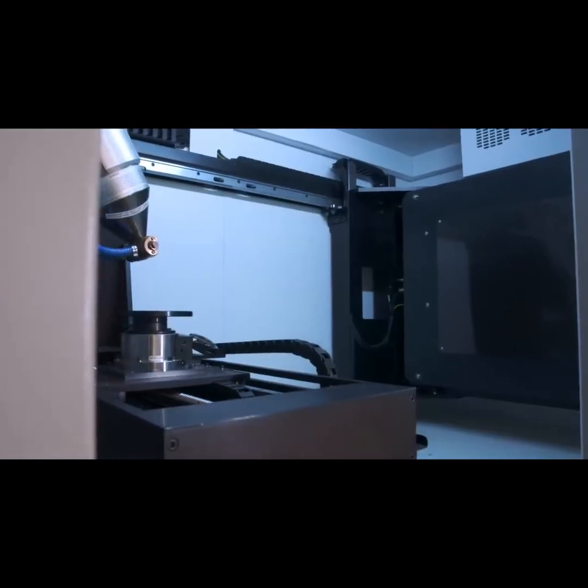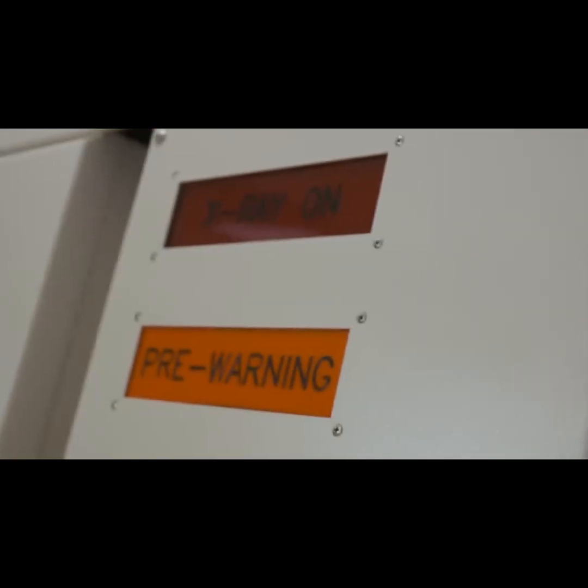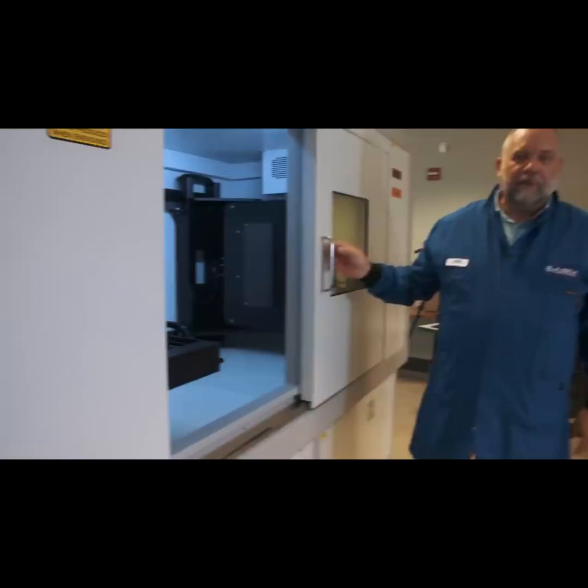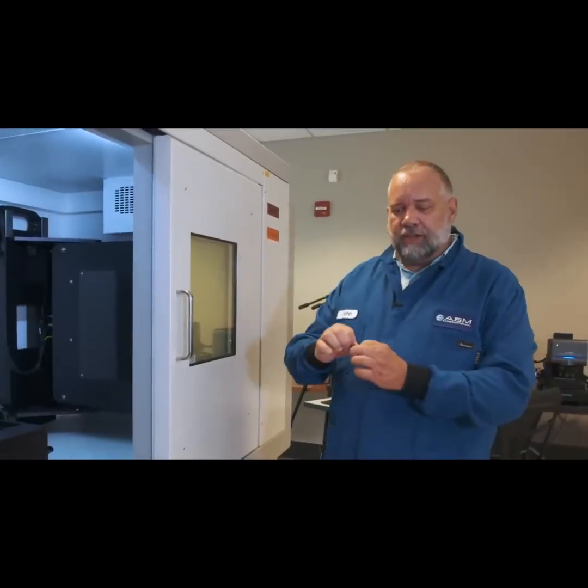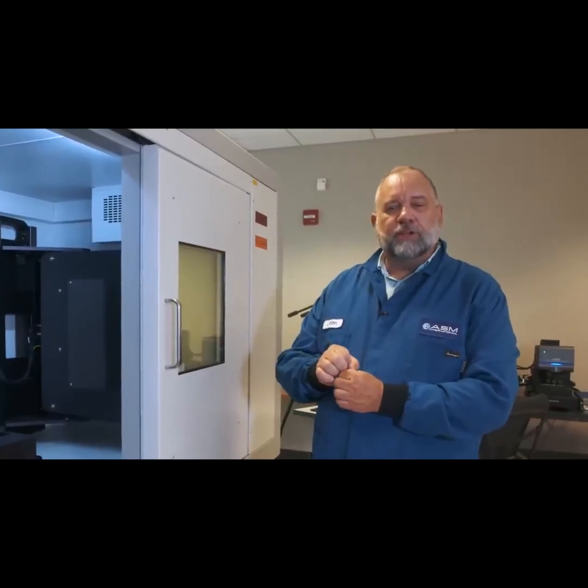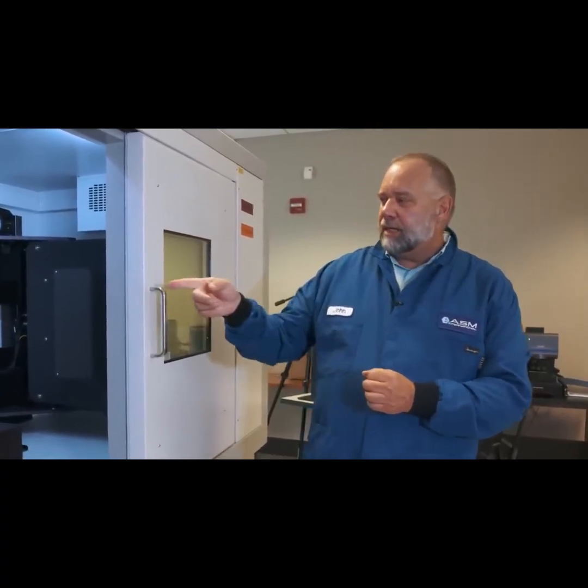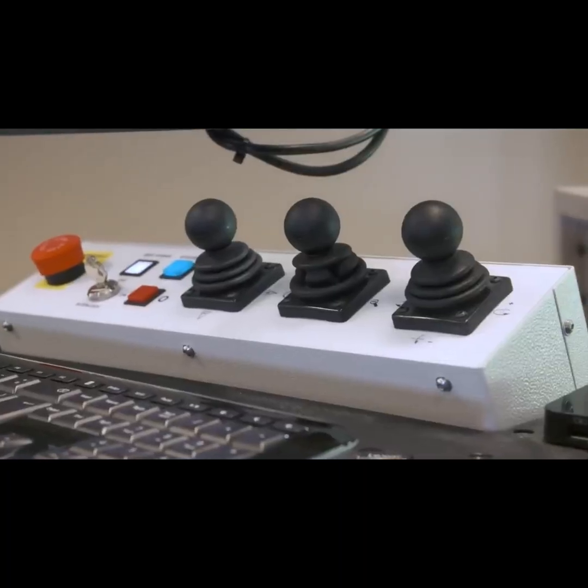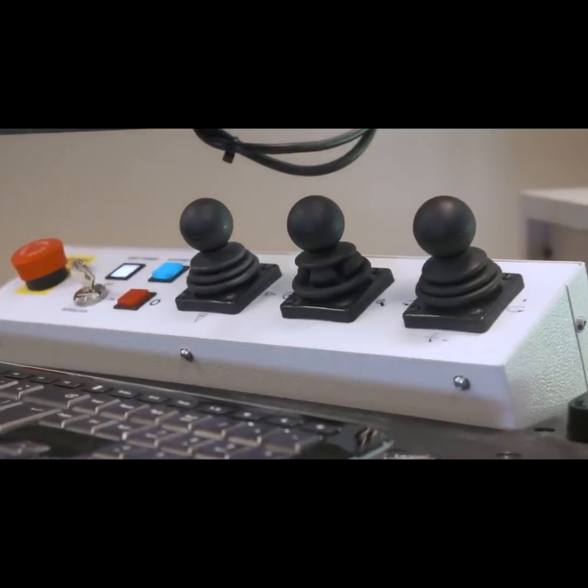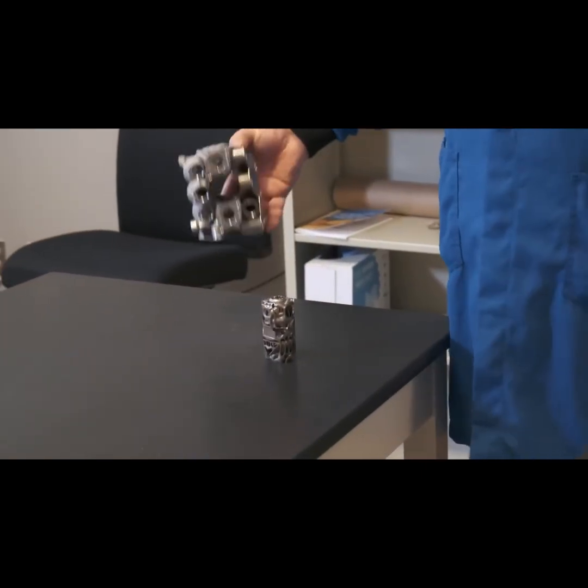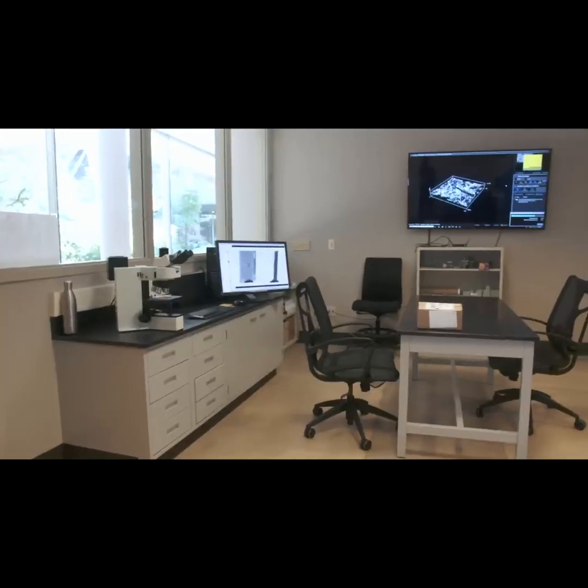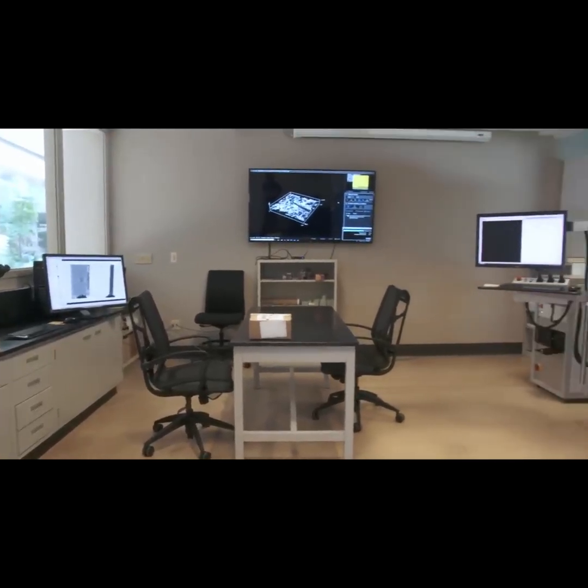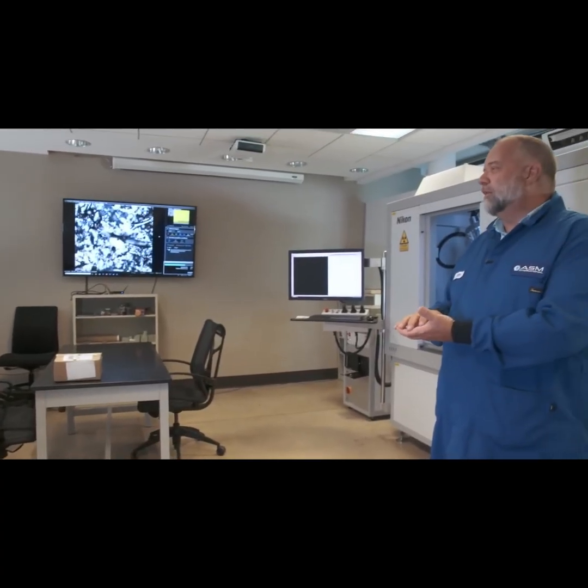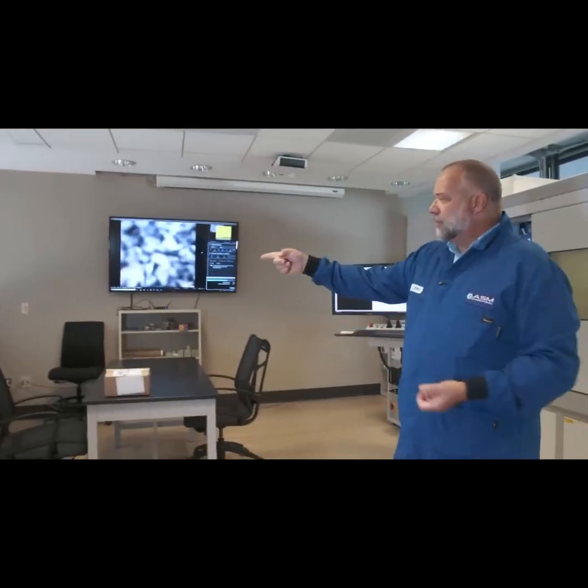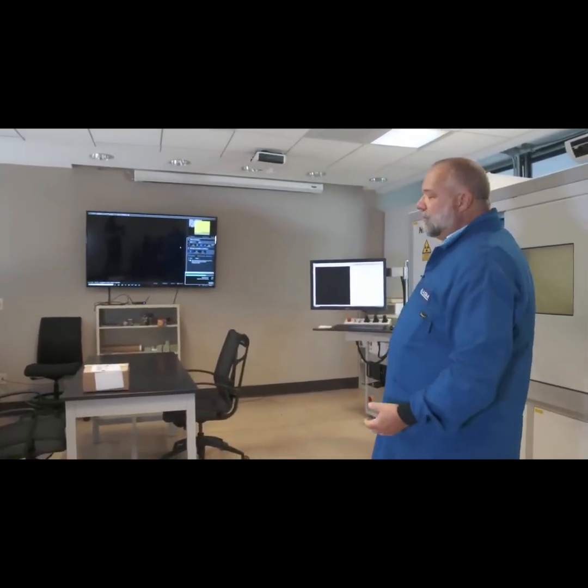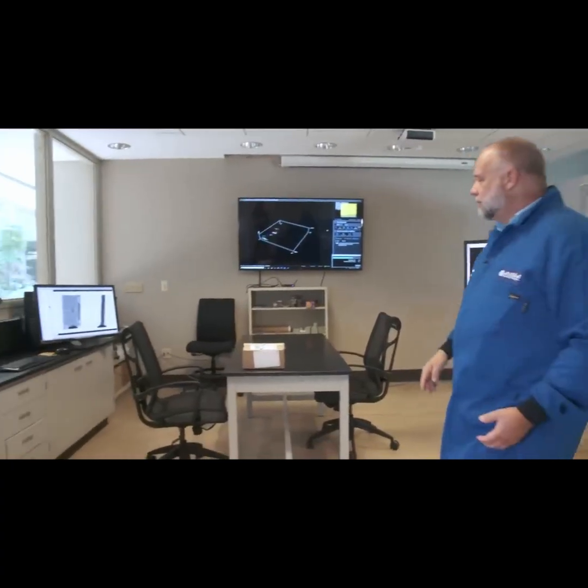When it hits the target, it's knocking electrons out of the atoms. The atoms fall back in and give off X-rays. That panel in the back is a detector, 2,000 by 2,000 different pixels. They're 0.2 millimeter round pixels that detect the energy of the X-rays. So the CT scanner has the resolution to look at powders and the penetrating capability to look at some parts. You capture the images over here, but you need a lot of horsepower to create these volumes and query them. And that's what this is, a reconstruction computer, taking the data from a CT scanner and creating something useful.